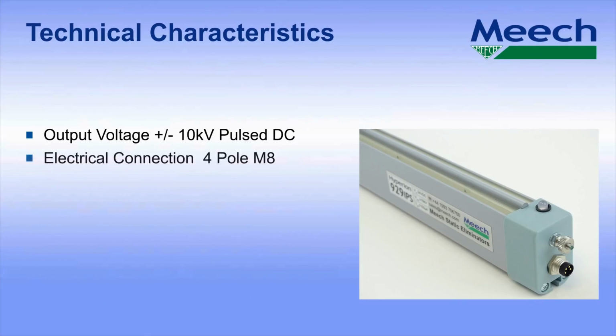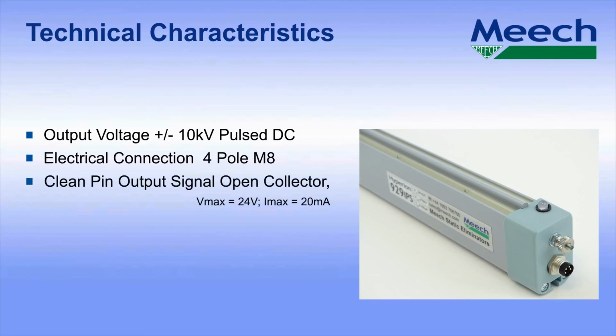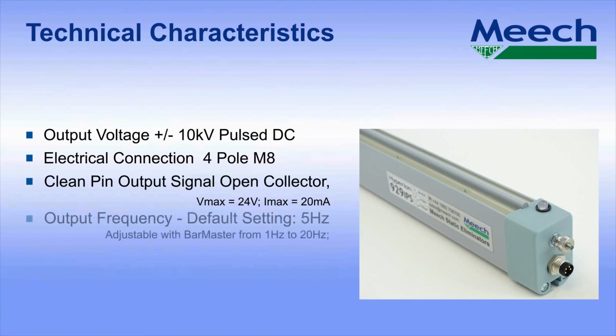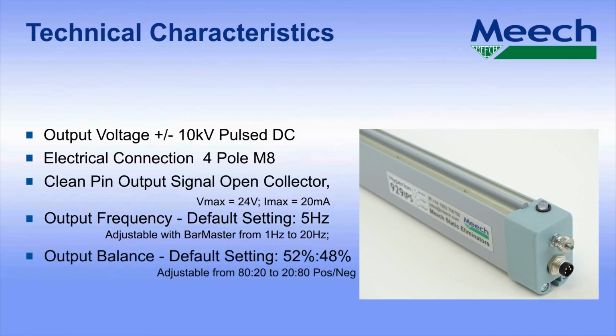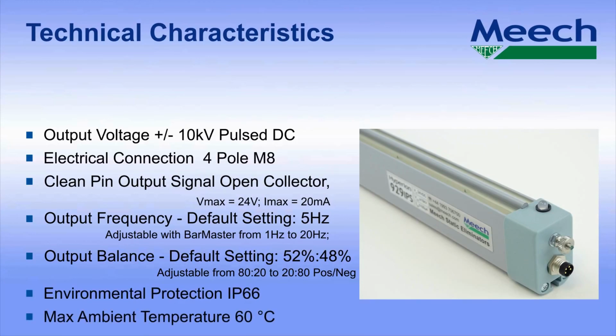Electrical connection is by a 4-pole M8 industrial Ethernet connector. The clean pin output signal is an open collector output with a maximum voltage of 24 volts and a maximum current of 20 milliamps. The default output frequency is 5 Hz, but is adjustable from between 1 and 20 Hz using the optional Barmaster programmer. As standard, the unit has a balanced output, but this can be biased either positive or negative using the Barmaster programmer to suit the application. Environmental protection is IP66. The unit has a maximum ambient temperature rating of 60 degrees C.